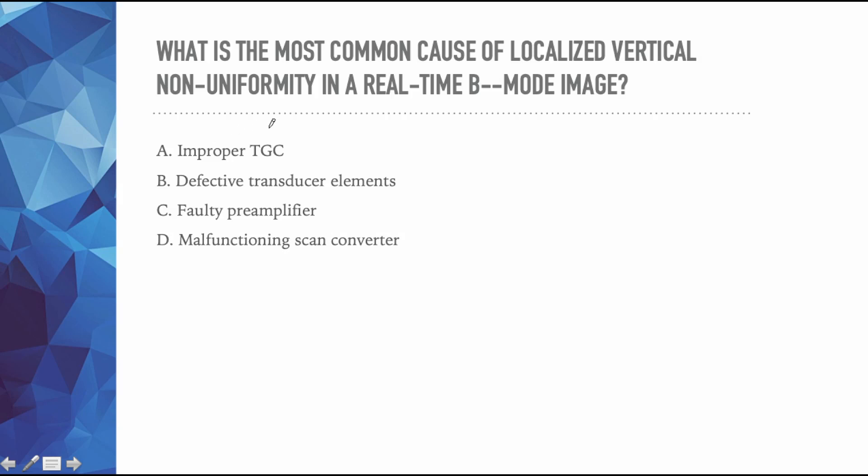All right. What is the most common cause of a localized vertical non-uniformity in a real-time B-mode image? There's a lot of keywords in here. So we're looking for the most common. We're looking for localized and this is a big word - vertical non-uniformity in a real-time B-mode image. So if we have our image this is saying localized, so it's going to be one area and it's vertical. So to me that would look like stripes. I'm thinking there's some stripes in this image. Why are there stripes in this image? If this was horizontal, we'd have stripes running this way. So we're looking for vertical non-uniformity in a real-time image. It's not frozen, it's moving.